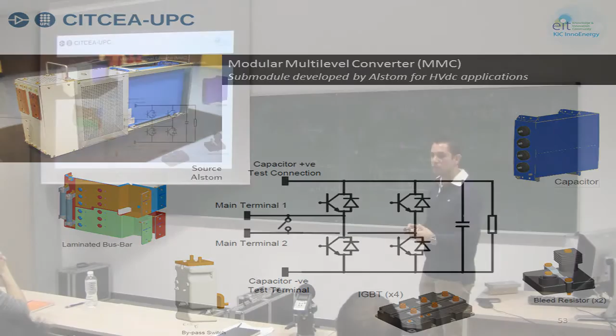For the IGBTs, this is a bypass switch. Since you have a series connection of submodules, if one fails, you just bypass it and continue converter operation—something that didn't happen in previous generations, where if one IGBT blew up, the whole converter shut down. This is because it's modular, and it's more efficient as well.